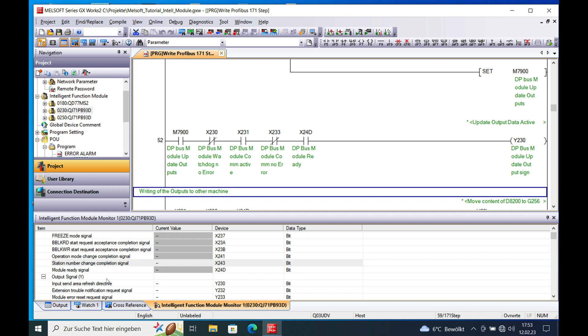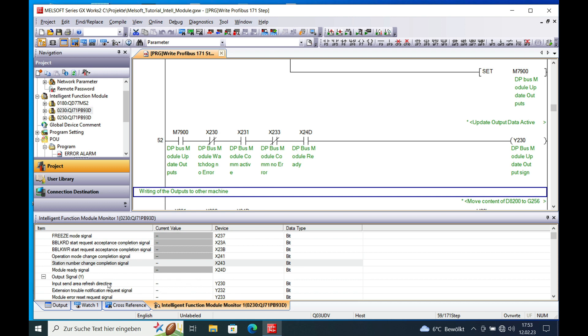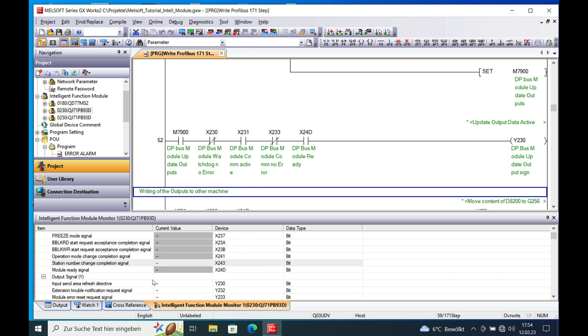And then you program the Y0 which is the input data being refreshed. That means the input data being sent to the master module. It's a little bit different because I would say this is an output, but anyway, it's the input data that being received by the master. And this is actually the output from the DP module to the DP bus master.